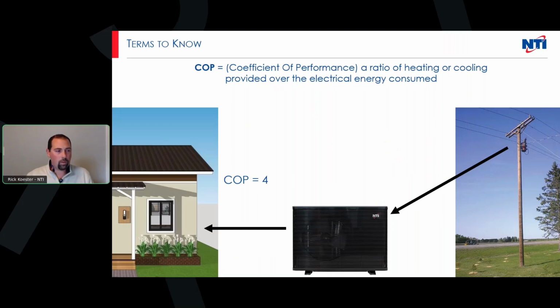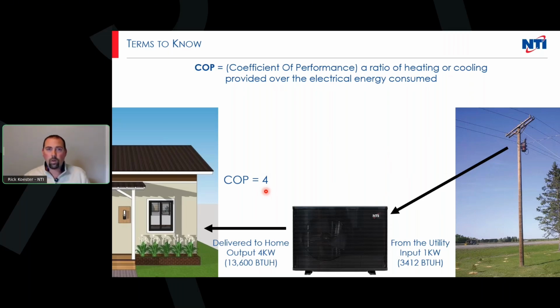Well, with a heat pump, we look at COP as our efficiency metric, and that's a ratio between the input and what we're actually putting into the space. So if I were to tell you our system had a COP of 4, what that really means is that for every 1 kW of input power, we're going to provide 4 kW of output power into that space. Looking at it BTU-wise, 1 kW is equal to about 3,412 BTUs. We put that into the machine, we absorb a lot of energy from the air, and we boost it up a little bit and put it into the space. And now I'm delivering 13,600 BTUs.